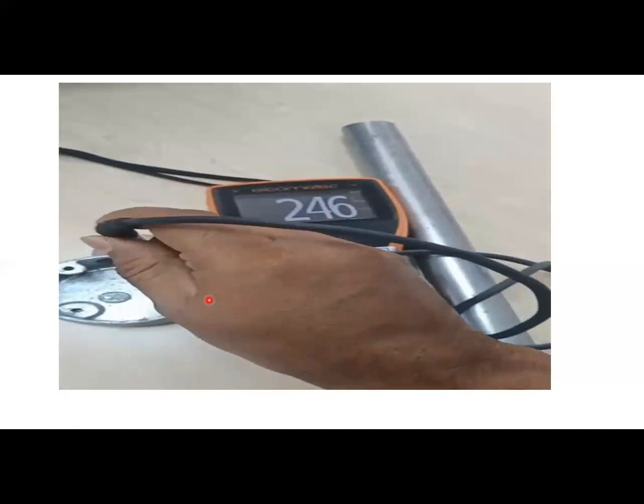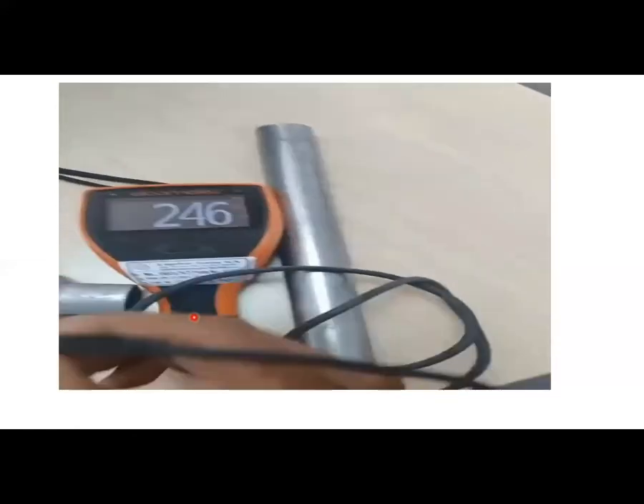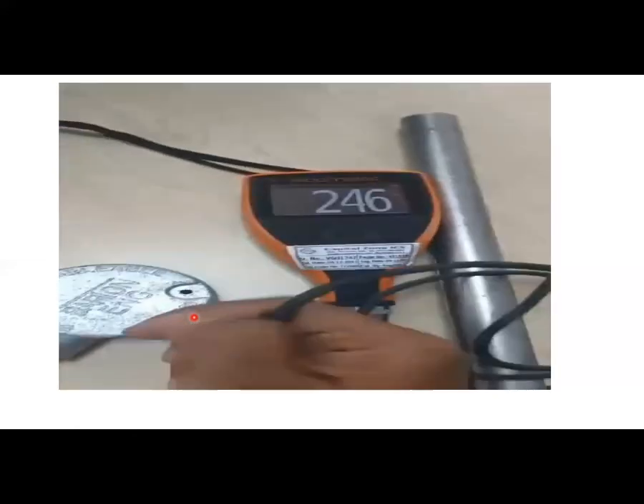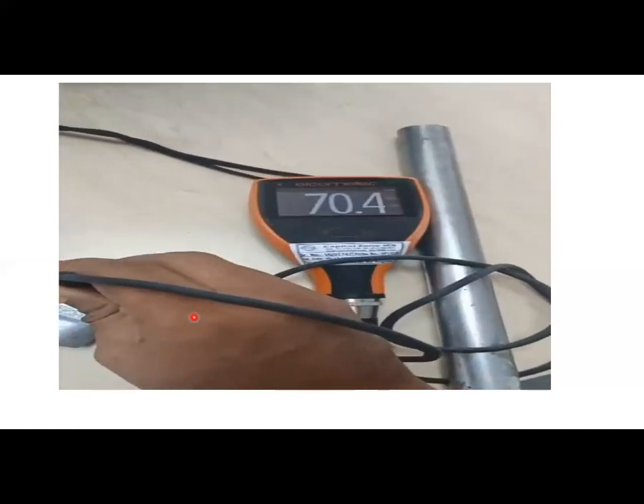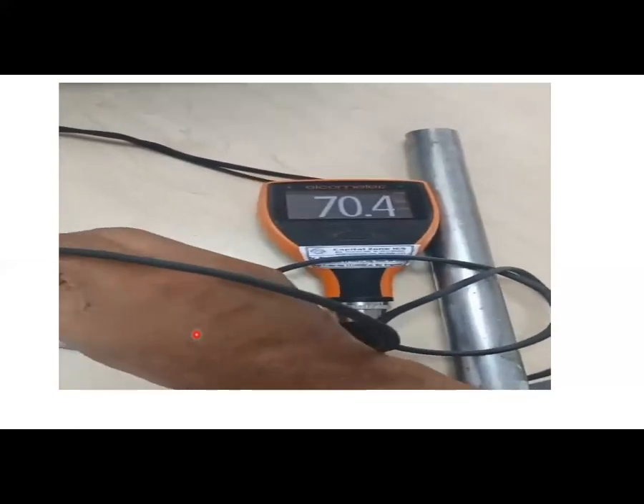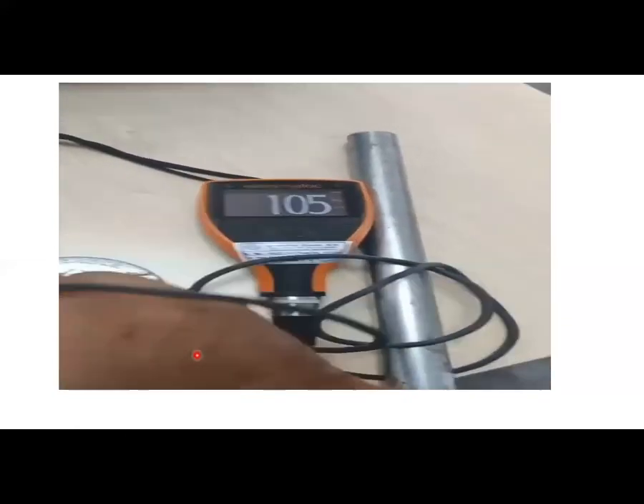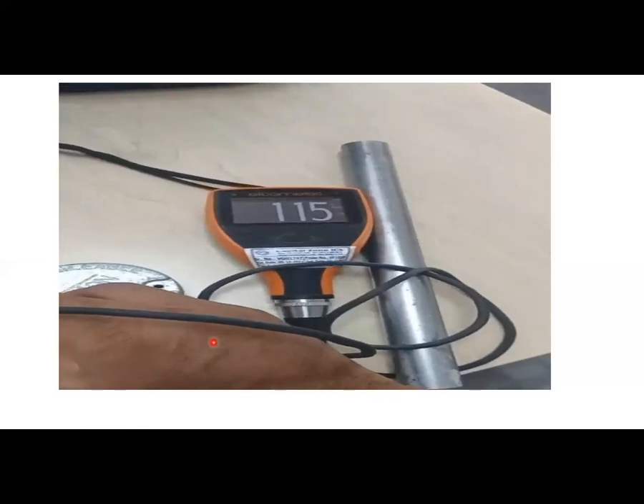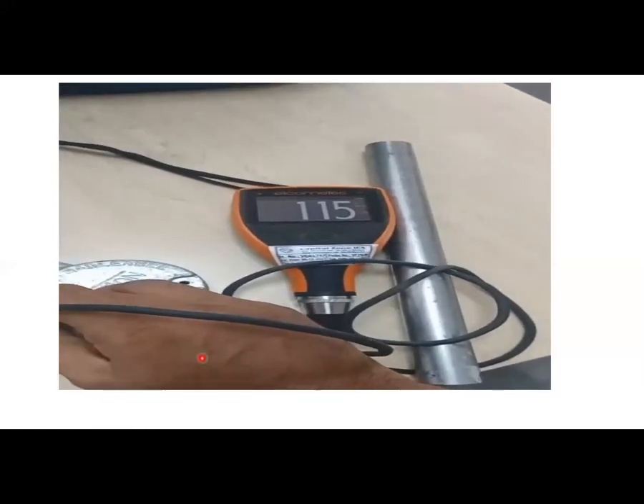This is how we are going to test galvanization coating thickness. We are checking randomly four or five different points and we will average the values.